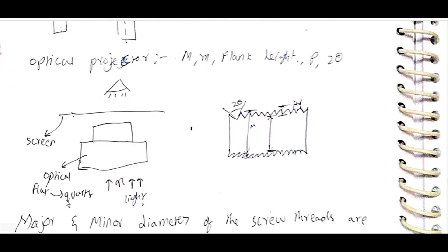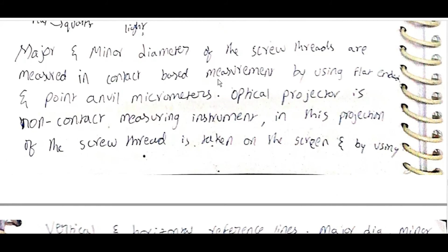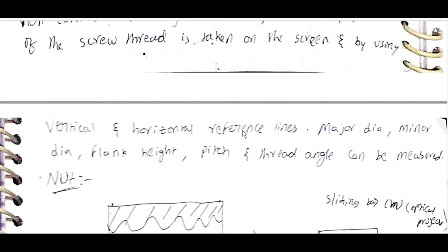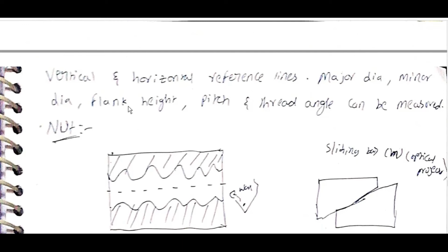Major and minor diameters of screw threads are measured in contact-based measurement by using flat-ended and point anvil micrometers. The optical projector is a non-contact measuring instrument. In this, the projection of the screw thread is taken on the screen, and by using vertical and horizontal reference lines, major diameter, minor diameter, flank height, pitch, and thread angle can be measured.